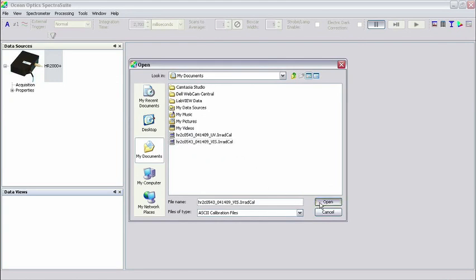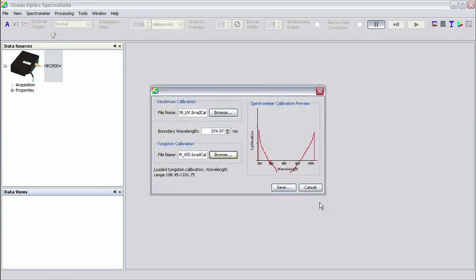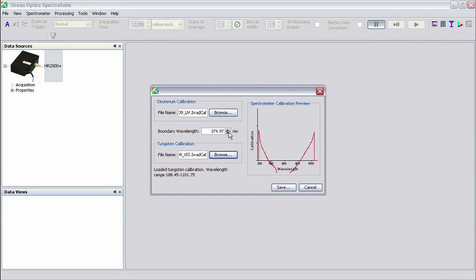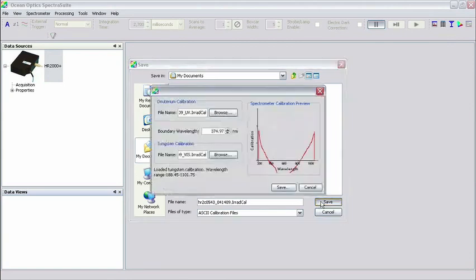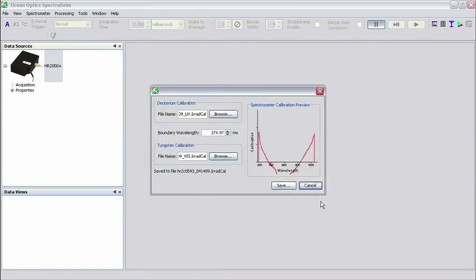Spectra Suite will automatically select the optimal boundary wavelength for combining these files. If you wish to manually select this boundary wavelength, you can use the up and down arrows to alter the wavelength value. Once you've loaded the two files, click Save. Naming your file and saving it will bring you back to the previous window, which you can now safely close.